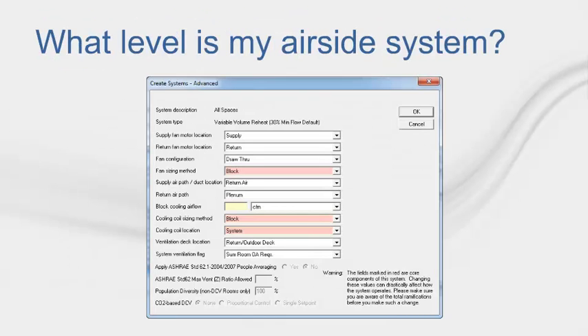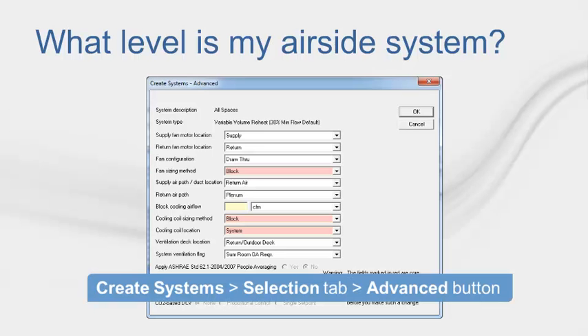Before jumping into the Assignments section, the first thing we need to figure out is what level our coils and fans are for our air side system. We need to navigate to the Create System section, Selections tab, Advanced button, Cooling Coil Location field. This will read either System, Zone, or Room. After knowing this, we can start assigning.